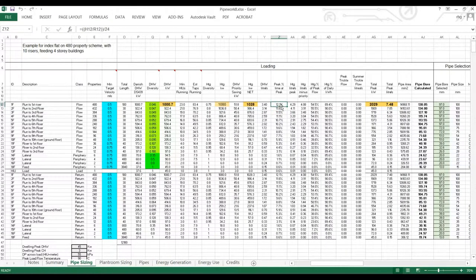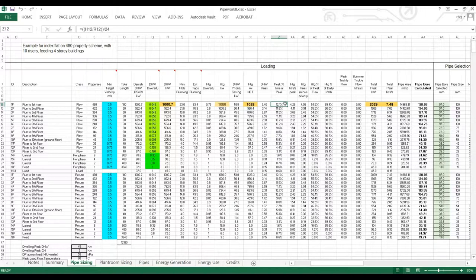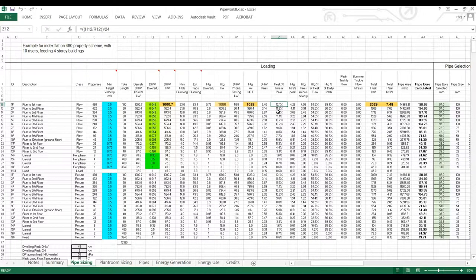We have a column that's the peak percentage time peak. So this is bringing into account the total amount of hot water used per day. So if we were running at peak diversified load for 12.1% of the time, we would deliver a full day's domestic hot water load. This is used in erosion calculations.